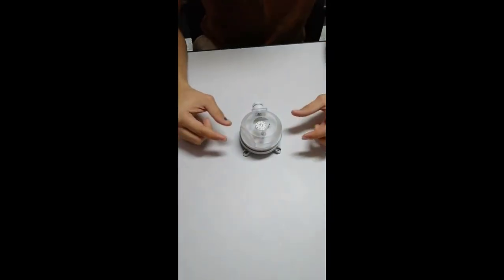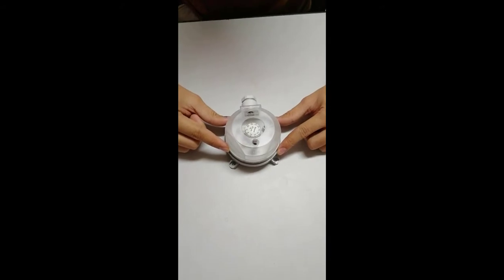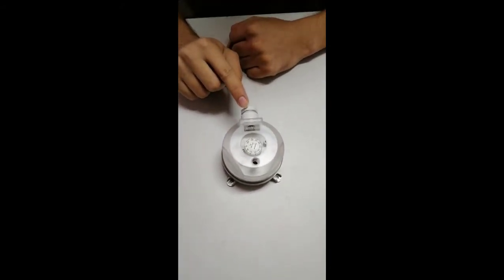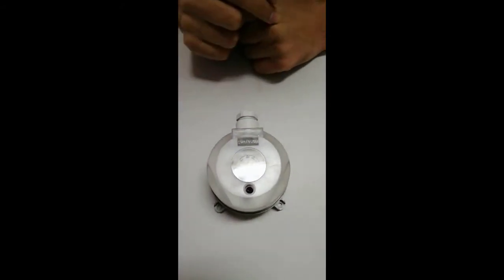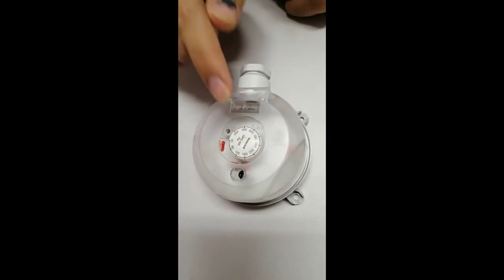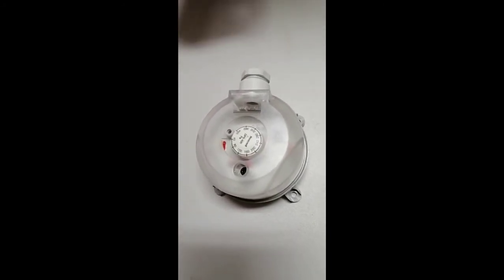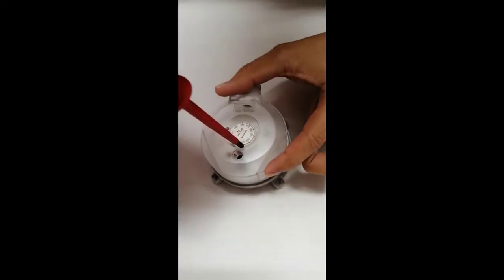So in this video we will talk about connections of different field devices. This is a differential pressure switch, air differential pressure switch, and this device is from Honeywell and the model number is DPS 400. So let's open this to check the connections.